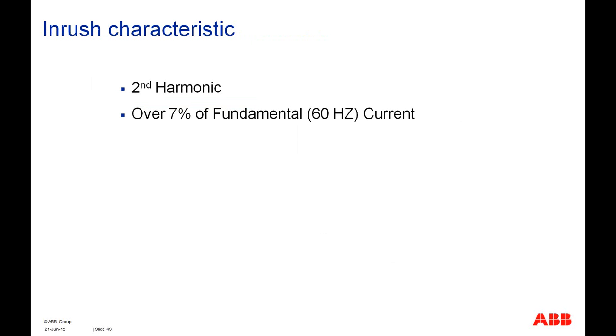So the way it is done is to filter out the second harmonic component of the current, and if it is more than a certain threshold value, which is a setting in the line differential protection scheme, then the differential protection will be blocked for that particular period of time.